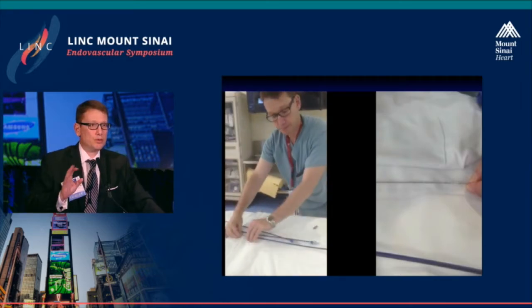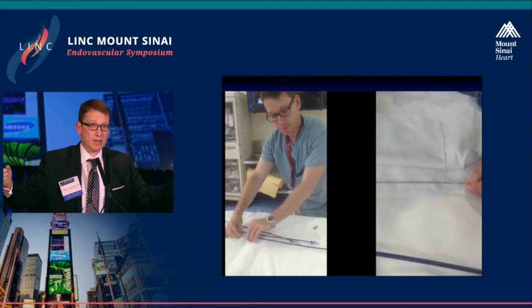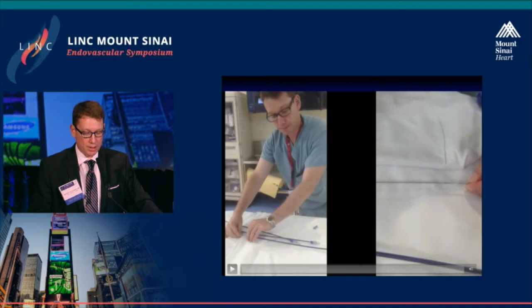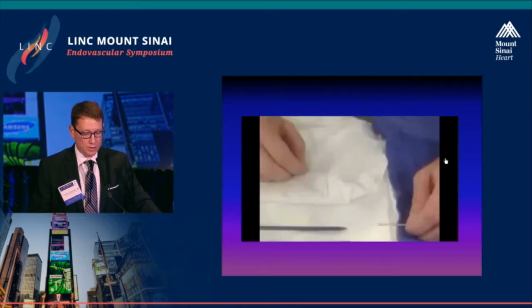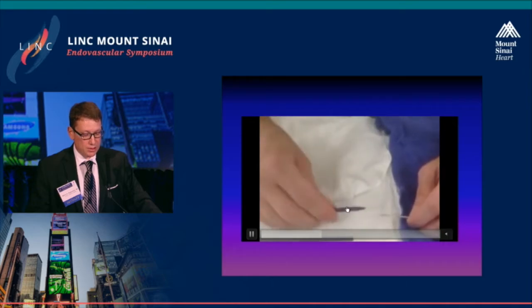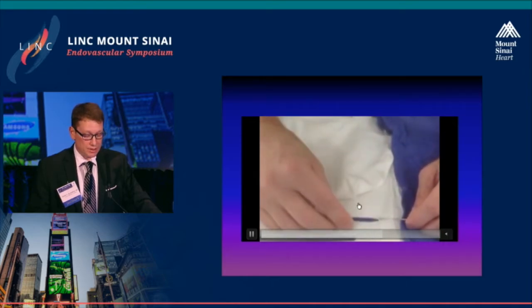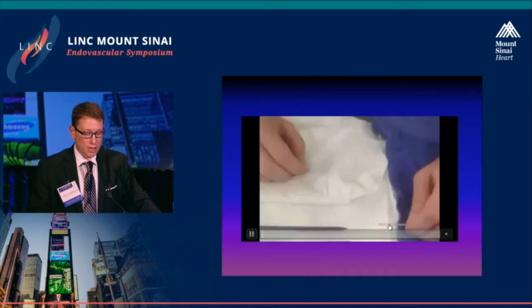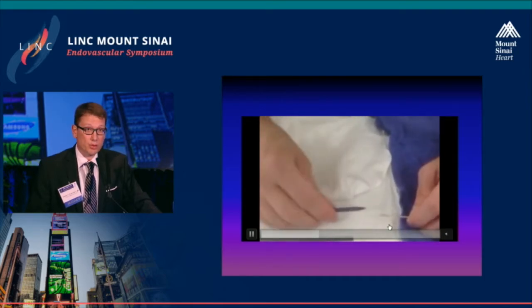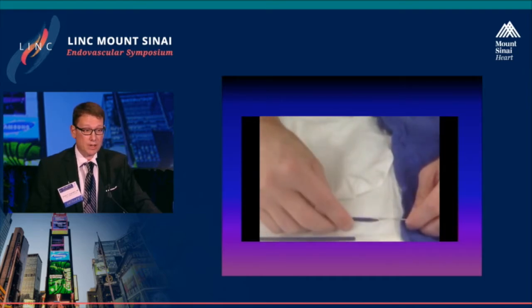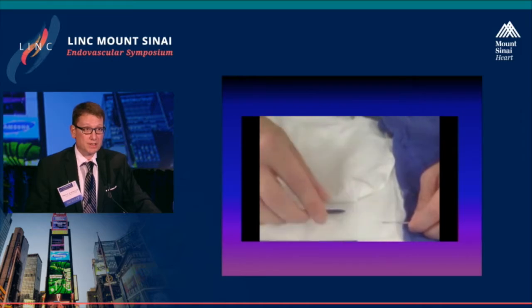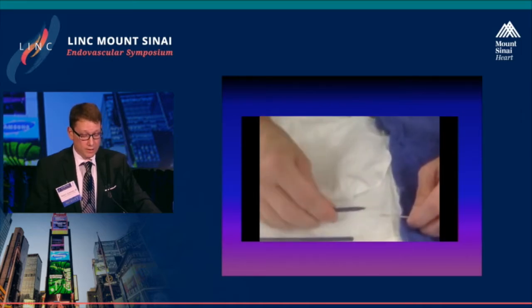A lot of people know that the Amplatzer cables can screw into each other and become an exchange-length cable. But here's where people think they're out of the woods, but they're not: the standard dilator that goes with the delivery sheaths for these devices goes over an 038 wire, but these cables can go up to 0.088 in diameter. So you can't actually put the dilator and the sheath over the cable.